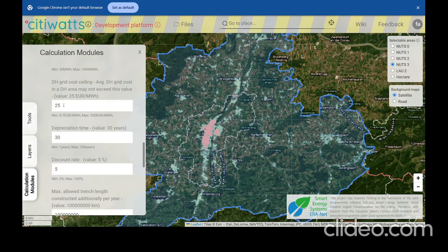Another parameter that you need to provide is the district heating grid cost ceiling. This value shows that the average network cost within every single district heating area may not exceed this value. So in my case, I am going to provide 45 euros per megawatt hour to see if I get any reasonable area for my district heating or not.